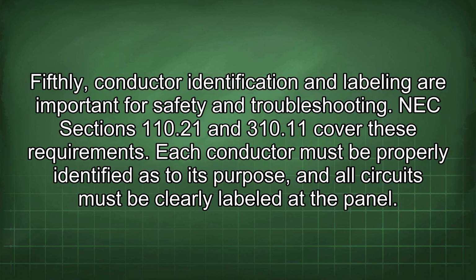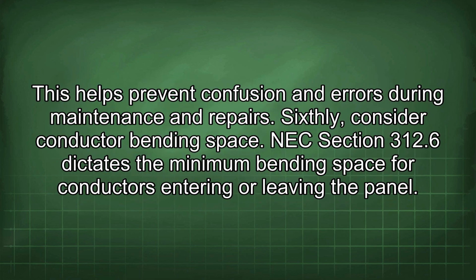Fifthly, conductor identification and labeling are important for safety and troubleshooting. NEC sections 110.21 and 310.11 cover these requirements. Each conductor must be properly identified as to its purpose, and all circuits must be clearly labeled at the panel. This helps prevent confusion and errors during maintenance and repairs.